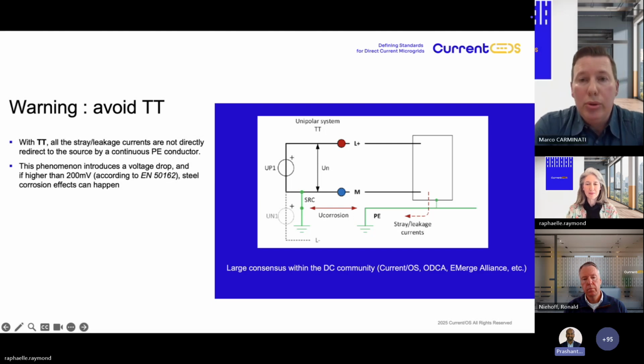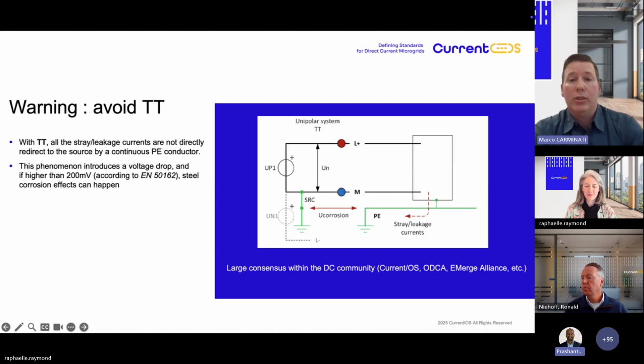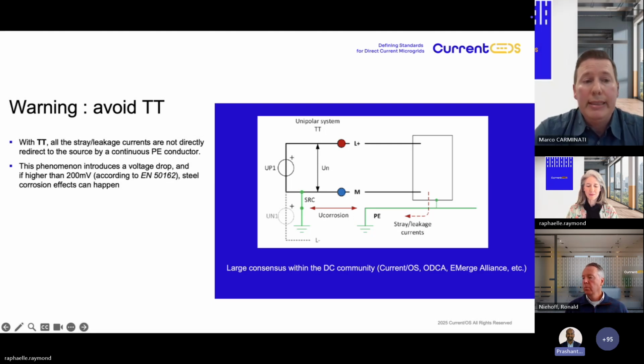So in order to dramatically reduce the risk of corrosion in DC, we avoid the usage of TT. And basically, there is a consensus within the DC community on this recommendation. Why? Because with a TT system, all the stray leakage currents are not directly redirected to the source through a continuous PE conducting path, as you can see in the picture, but through the ground. This phenomenon introduces a voltage drop which can be higher than 200 millivolts, which is the limit, according to the standard EN 50162, for not having a corrosion risk. If it is higher, like in a TT system, there could be a risk of corrosion.